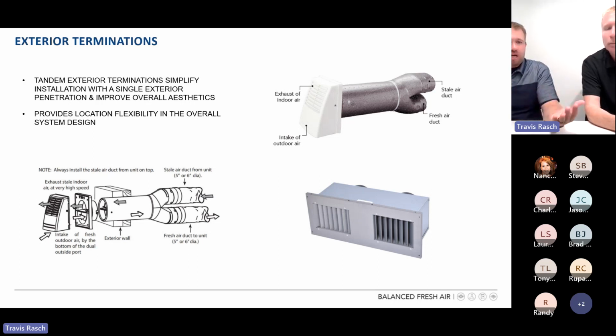We as manufacturers, among others, do validation to check the contamination rate, meaning how much of the stale air from the H or ERV gets drawn back in. From a design and airflow standpoint, we stay well below the thresholds ASHRAE has set for different applications. So just know these exist. You're not always confined to putting separate terminations in two different areas. You do have the ability to use tandem terminations as well.